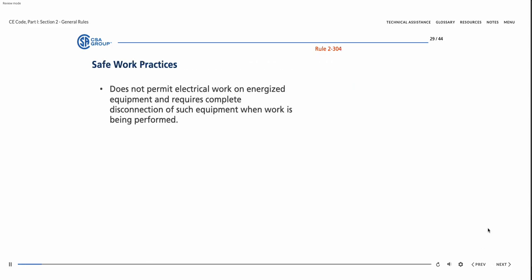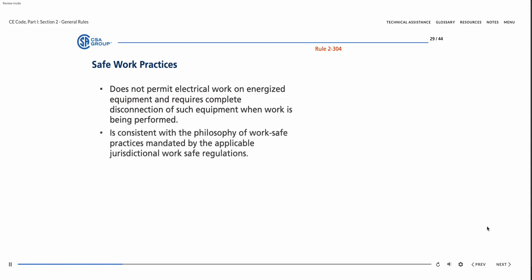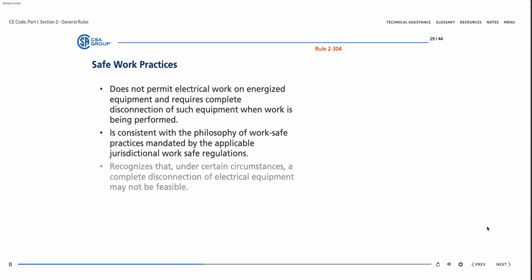Rule 2-304 does not permit electrical work on energized equipment and requires complete disconnection of such equipment when work is being performed. This code requirement is consistent with the philosophy of work-safe practices mandated by applicable jurisdictional work-safe regulations. The rule also recognizes the fact that under certain circumstances, a complete disconnection of electrical equipment may not be feasible. In such cases, work on live, energized equipment may be performed, as long as all necessary precautions consistent with the nature and extent of the electrical hazards are taken to ensure that the work can be performed safely.